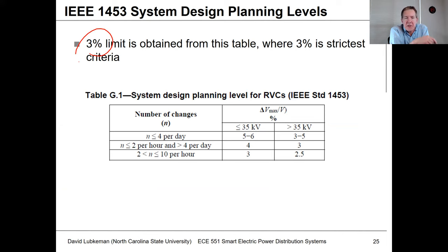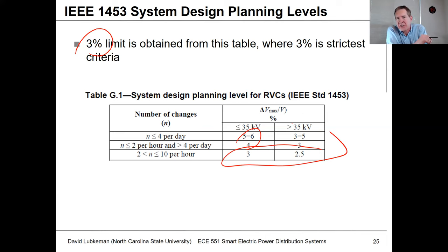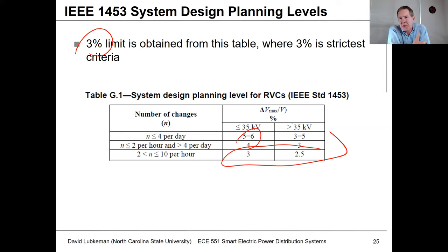3% is kind of your strictest criteria. If events are less frequent, you can maybe get by with larger percent changes. But typically, if you're doing a study, you're probably going to look at something between 2.5% and 3%. Each utility has slightly different takes on what they're going to use, but between 2.5 and 3% is what a lot of utilities look at in terms of voltage variability due to things like flicker for a PV system installation.